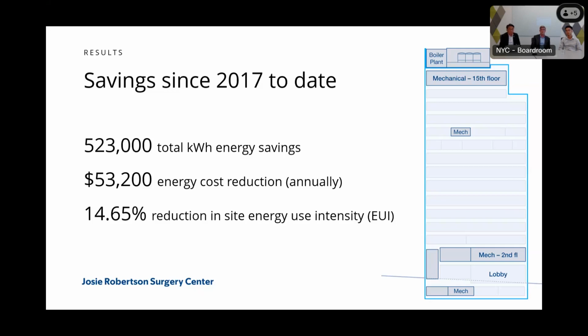These numbers are actually relatively typical for a utiliVisor project. Typically we see anywhere from 8 to 20% in utility reduction. That seems like a pretty wide range - it depends on the amount of information that utiliVisor is able to receive from the building. Sometimes a building will have multiple BMS systems, sometimes a building will be unable to even see the air handling units, you're just sending chilled water out into a loop and the loop does what it wants to do. Here at Josie Robertson we really got a nice full picture, and we were able to push the envelope at the site. There are still some items we want to pursue a little further, and hopefully we'll be able to push down the value even more.